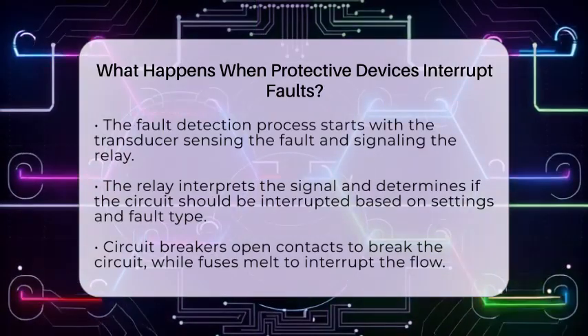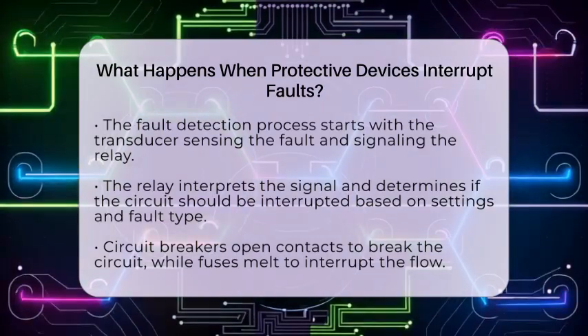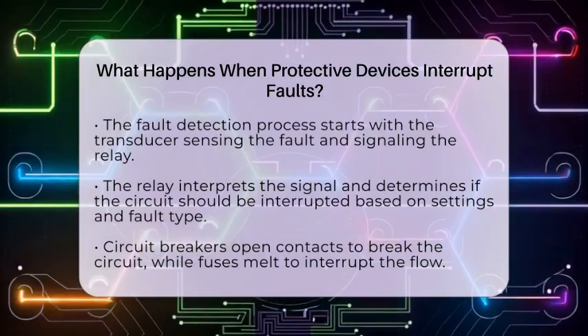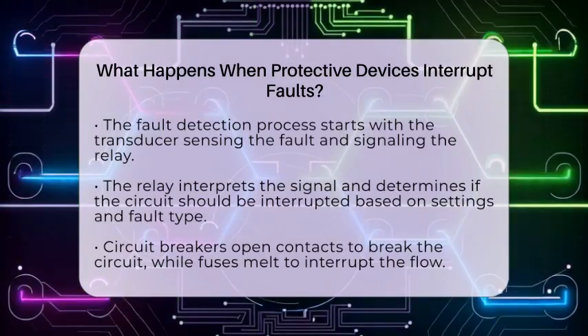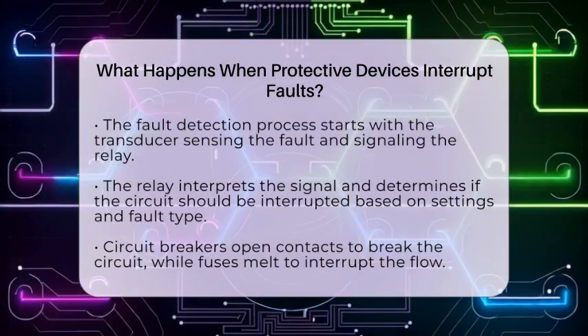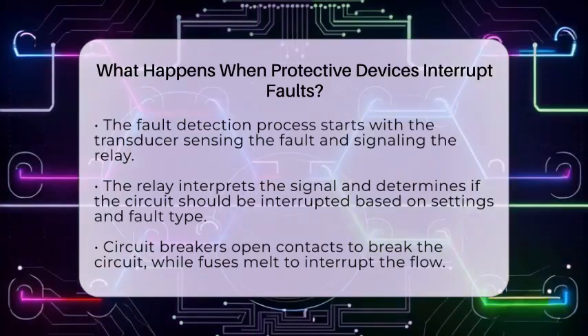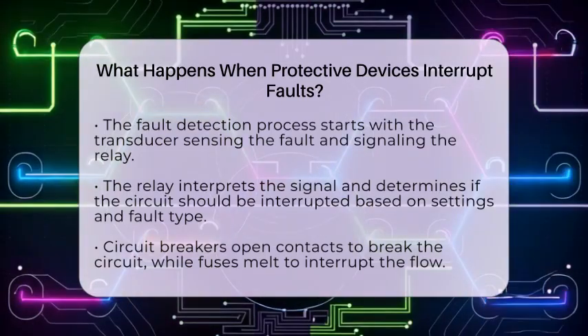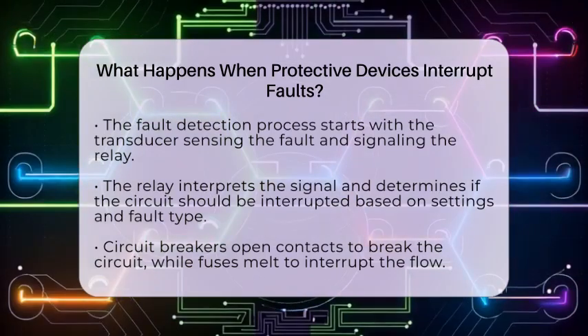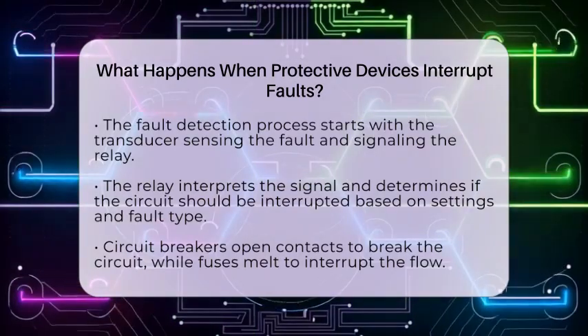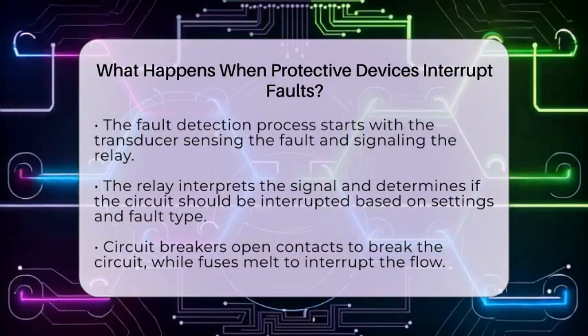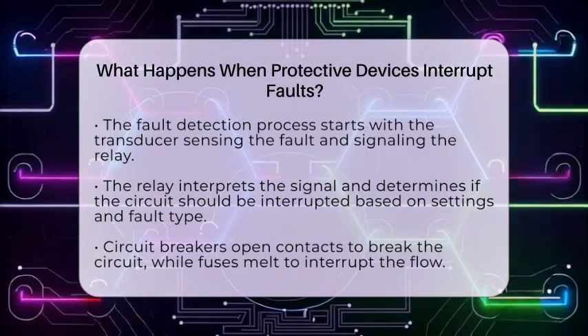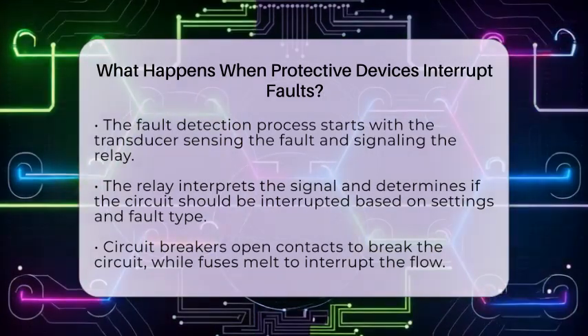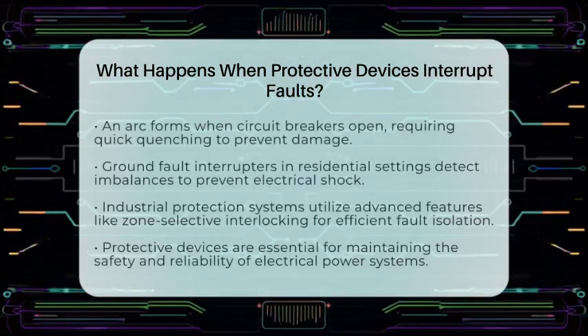When a circuit breaker opens, an arc forms between the separating contacts. This arc must be quenched quickly to prevent damage to the breaker or the system. The quenching process involves cooling the arc to deionize the gas between the contacts, allowing the circuit to be safely opened. In practical applications, the interruption of faults is critical to prevent equipment damage and ensure safety.